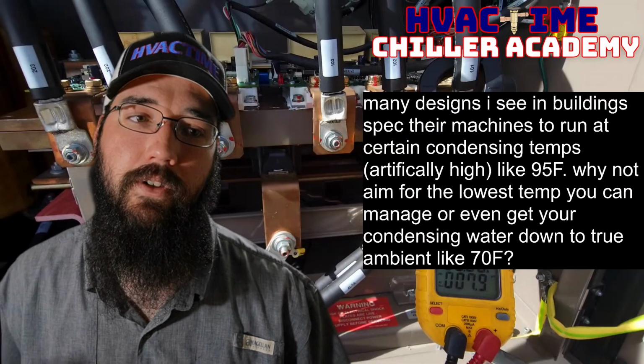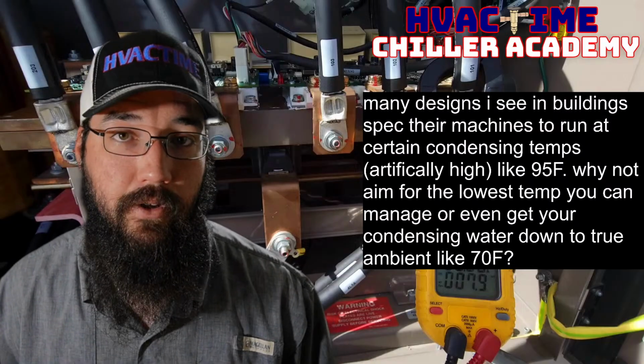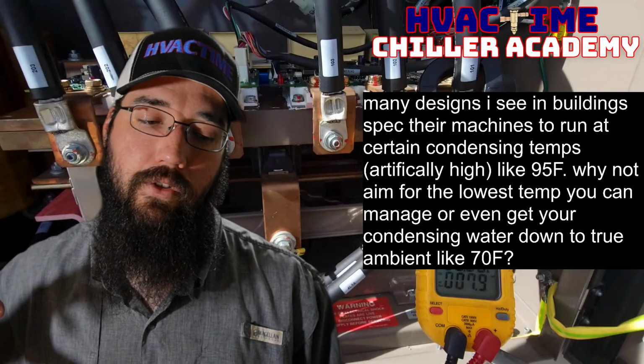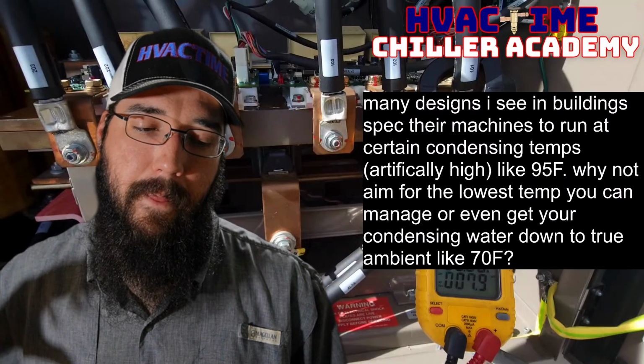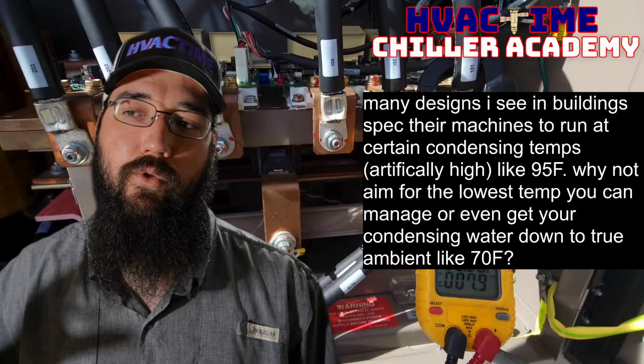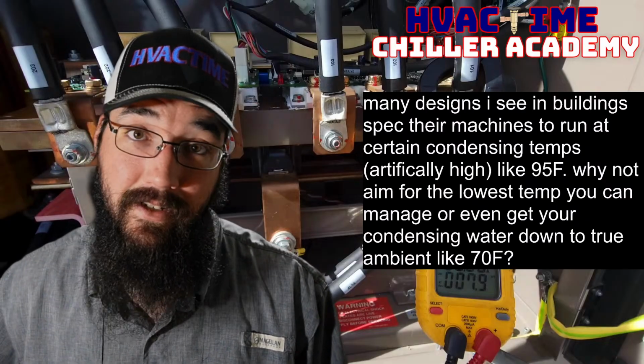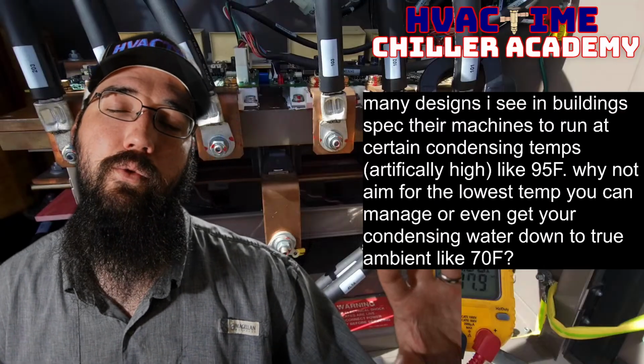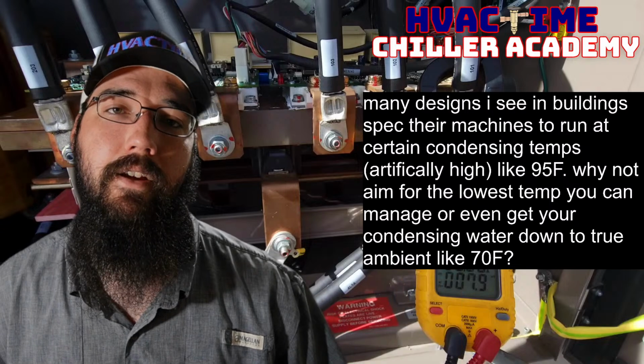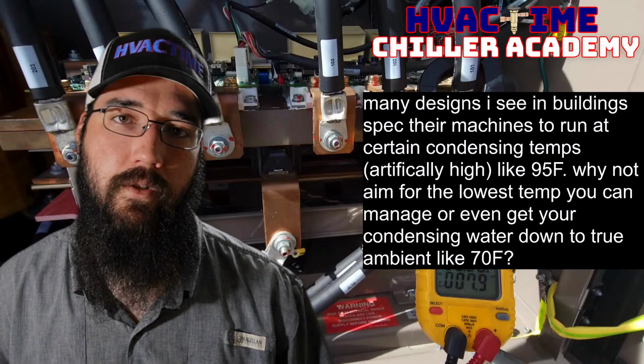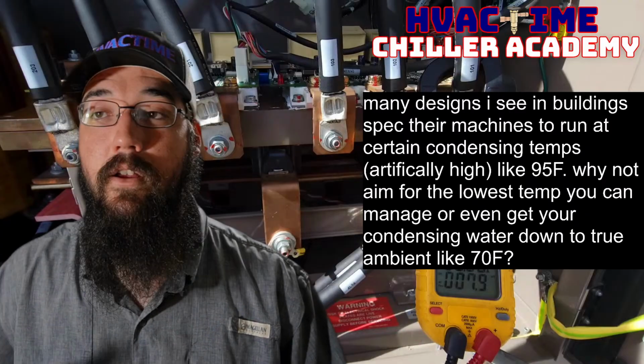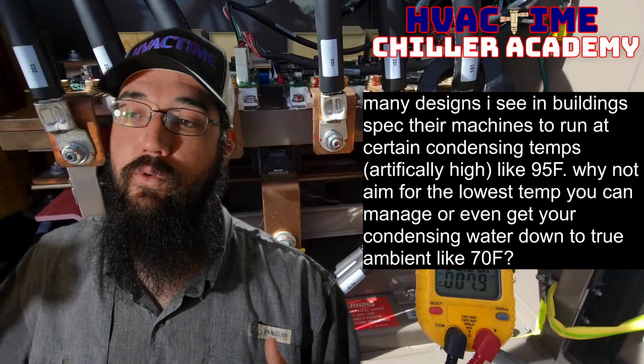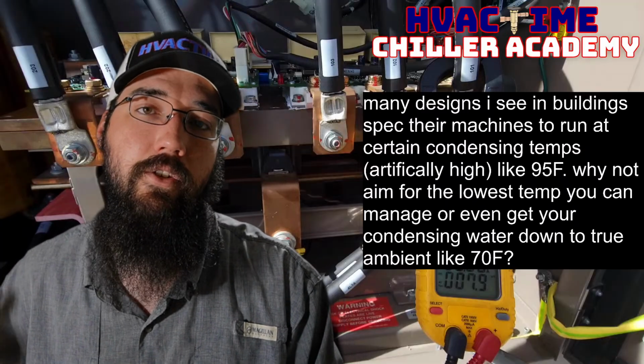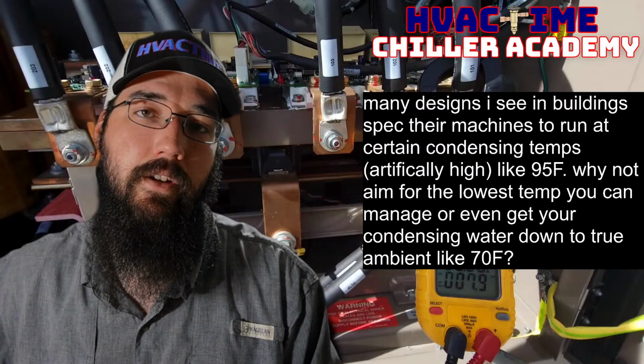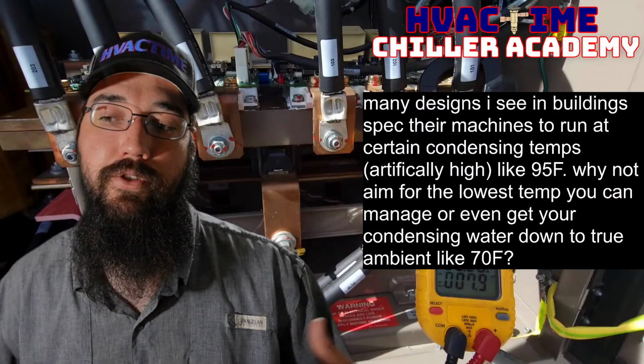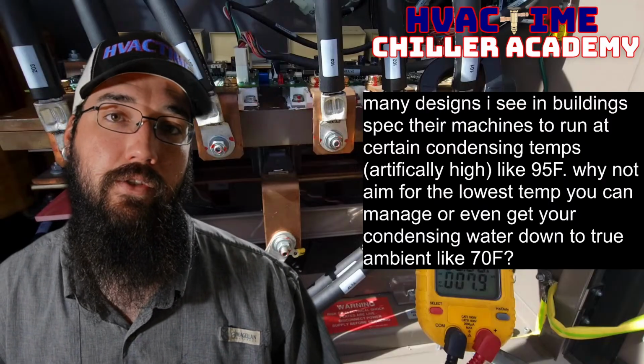Now, these aren't hard numbers. These are just examples, but this is realistic to what I personally have dealt with in these cases. And so it is way more efficient to put the extra load on the tower fan, and it's a hell of a lot easier to fix a tower fan motor than to try to service a chiller that's been beat to hell because we're trying to run high condenser waters. Whether it be a surging issue, that would be the worst case scenario, right? You're artificially trying to use less energy in your cooling towers by raising the condenser water set points, but now you've pushed your chiller to a point where it's more frequently surging.